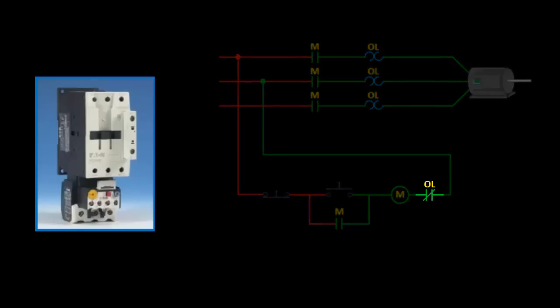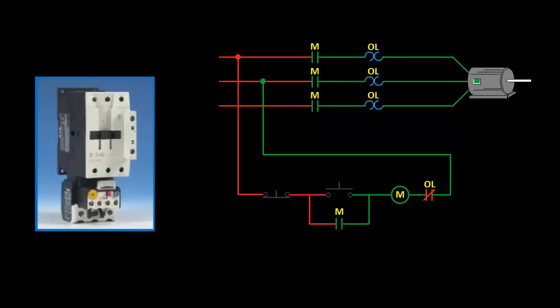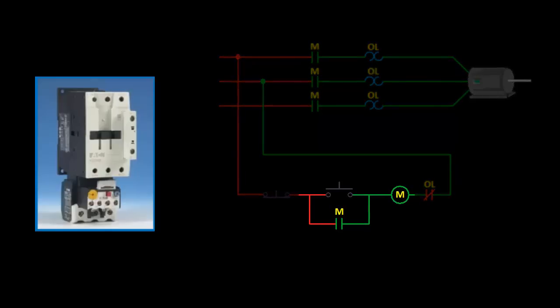In automatic reset, the contact will reset itself after a period of time after the trip, but in three-wire control, the motor will still have to be manually restarted as the starter coil remains de-energized.